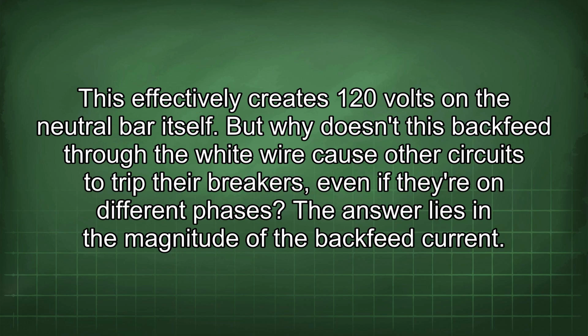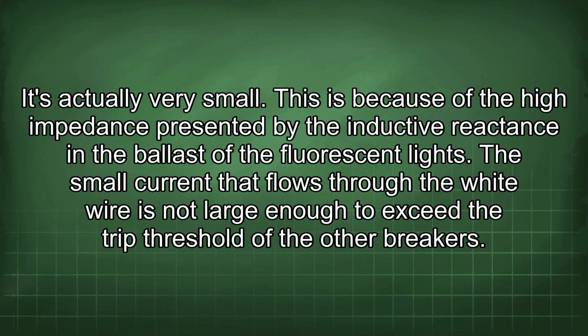But why doesn't this backfeed through the white wire cause other circuits to trip their breakers, even if they're on different phases? The answer lies in the magnitude of the backfeed current. It's actually very small. This is because of the high impedance presented by the inductive reactance in the ballast of the fluorescent lights. The small current that flows through the white wire is not large enough to exceed the trip threshold of the other breakers.